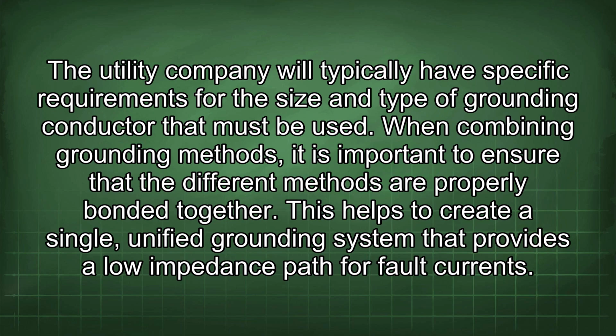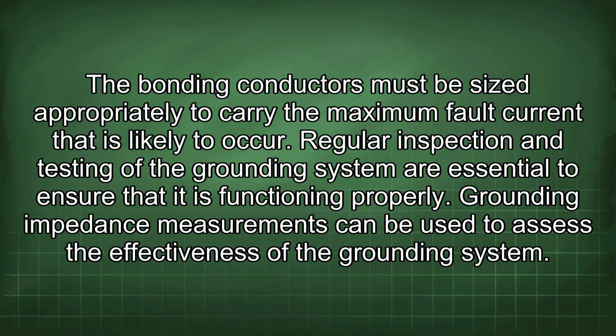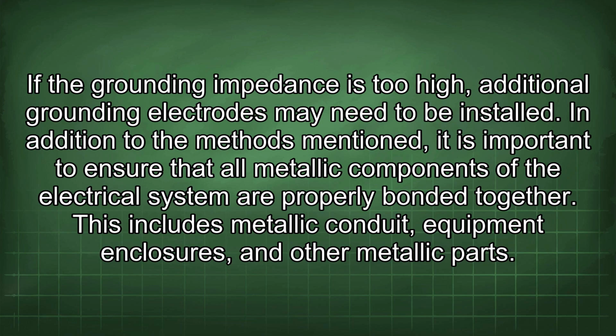When combining grounding methods, it is important to ensure that the different methods are properly bonded together. This helps to create a single, unified grounding system that provides a low impedance path for fault currents. The bonding conductors must be sized appropriately to carry the maximum fault current that is likely to occur. Regular inspection and testing of the grounding system are essential to ensure that it is functioning properly. Grounding impedance measurements can be used to assess the effectiveness of the grounding system. If the grounding impedance is too high, additional grounding electrodes may need to be installed.